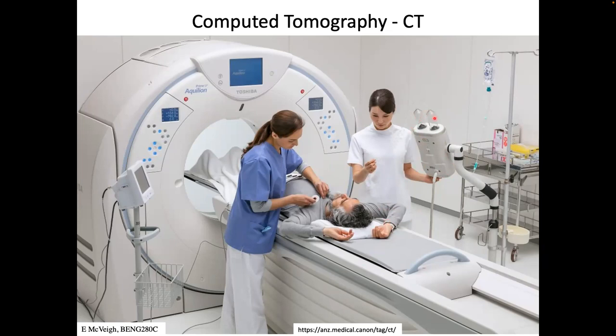There are two vials: one with contrast agent and one with saline. After pushing the contrast, you push about 50 cc's of saline behind it to flush it downstream into the heart. This injector is controlled from the scanner console — typically a separate company like Medrad provides it — and the tech pushes controls to start the injection, then starts acquiring CT data.